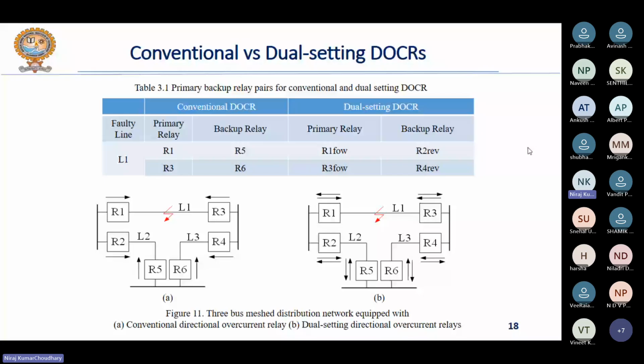In figure A, where the conventional directional overcurrent relays are used, suppose a fault occurs at any point on L1 in the system. This is the faulty line. Then what should be the primary relays? Suppose the primary relay is R1, then which relay should be the backup for this primary relay R1? R5 will be the backup relay because these are directional overcurrent relays, right? You cannot consider R4 here because the settings of the relays are always defined moving away from the bus to which the relay is connected. That's why you can see these directions mentioned. These directions represent that these particular relays will work only if the current flows in the direction shown here, right?